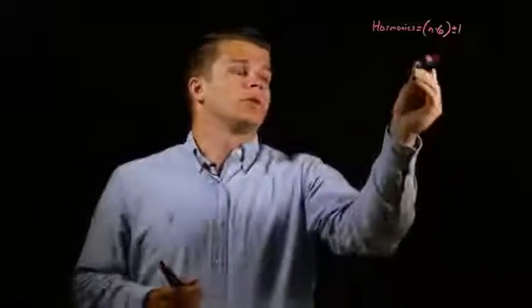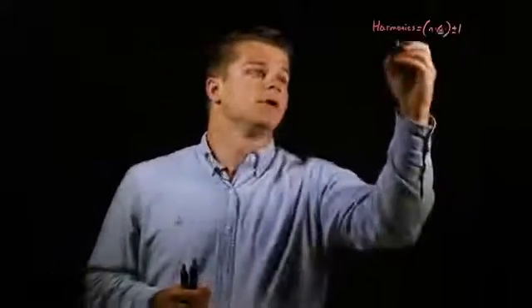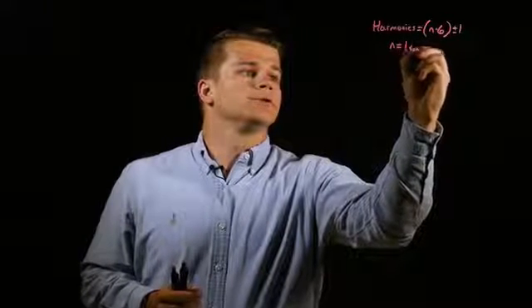Harmonics are integer multipliers of the fundamental frequency. Because our drive is a 6-pulse VFD, we would have a 6 here in this equation. But if you have a 12-pulse VFD, for example, you would replace this with a 12. And then n equals 1 to infinity.